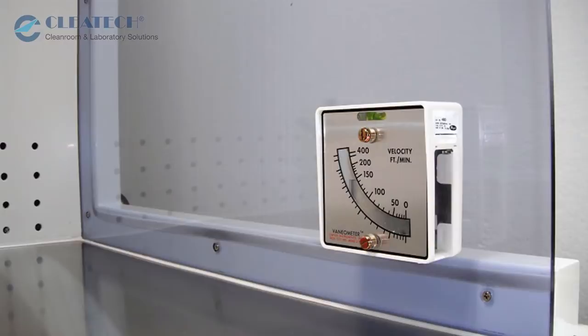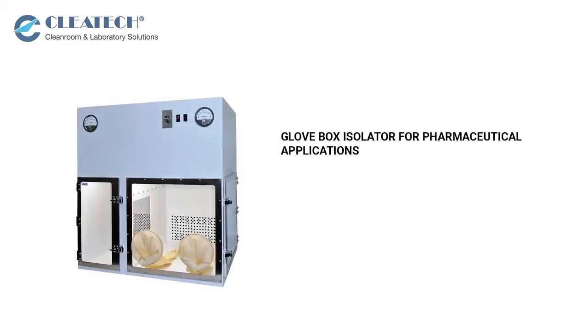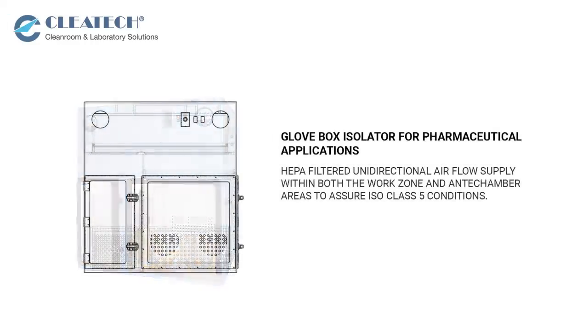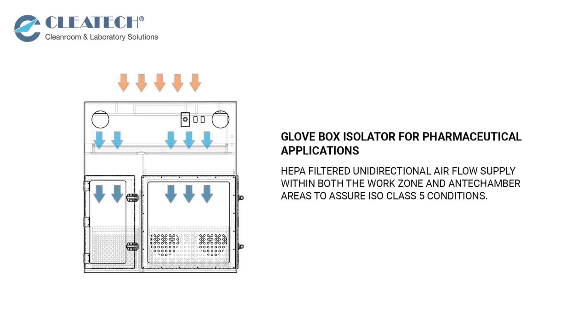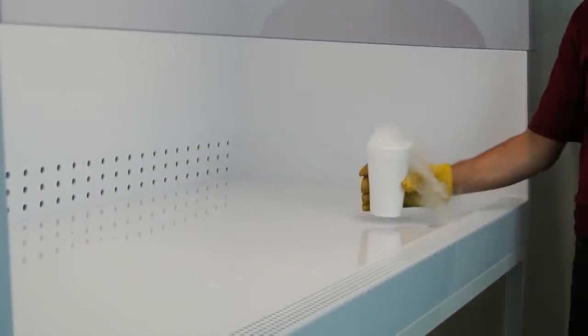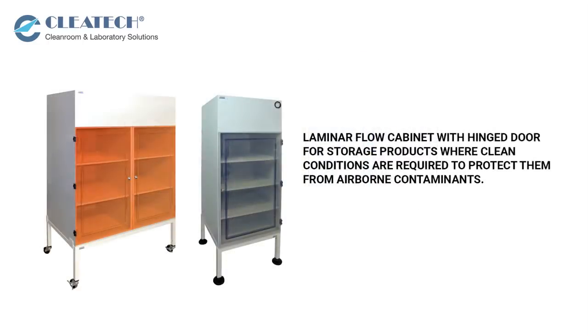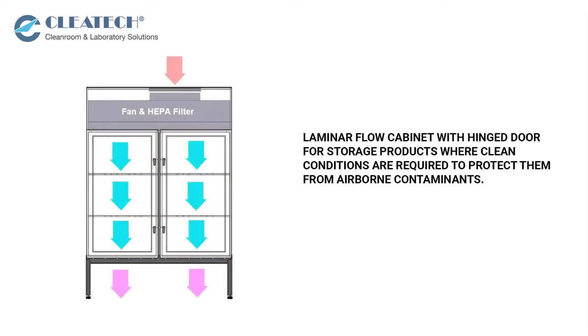Cleatech also offers specialty systems, including an airflow monitor and glove box isolator for pharmaceutical applications, with HEPA-filtered unidirectional airflow supply within both the work zone and antechamber areas to assure ISO Class 5 conditions. Additional options include a full exhaust laminar flow hood for protecting both operator and products, one-sided or two-sided access laminar flow workstations in bench top and floor mount styles, and a laminar flow cabinet with hinged door for storing products when clean conditions are required to protect them from airborne contaminants.